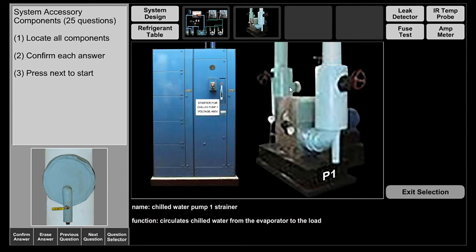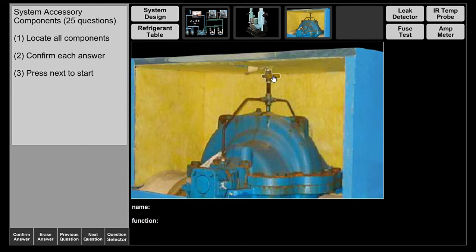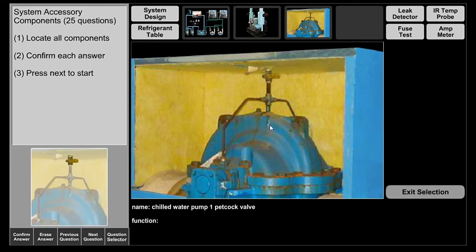As water comes through the strainer it enters the pump casing. Water comes in through the eye of the impeller, the impeller circulates it and discharges it out to the discharge line. Before the discharge line there is a petcock valve, also known as a vent valve. During seasonal startup, if there is air inside the volute you will have a cavitated pump that will not circulate chilled water properly throughout the entire system.